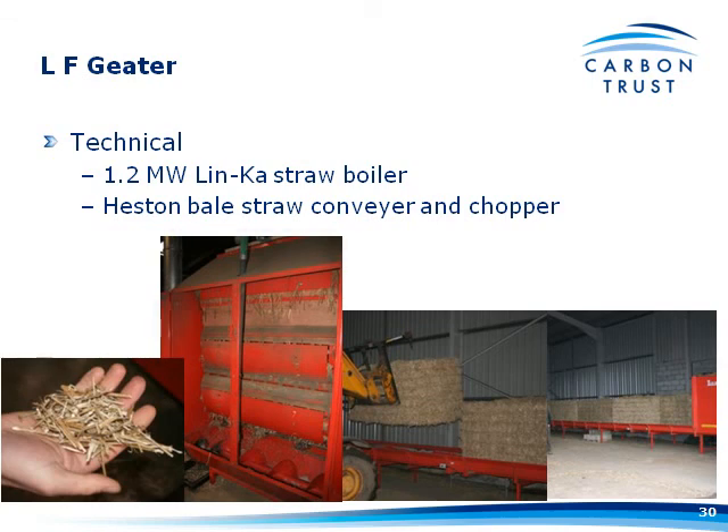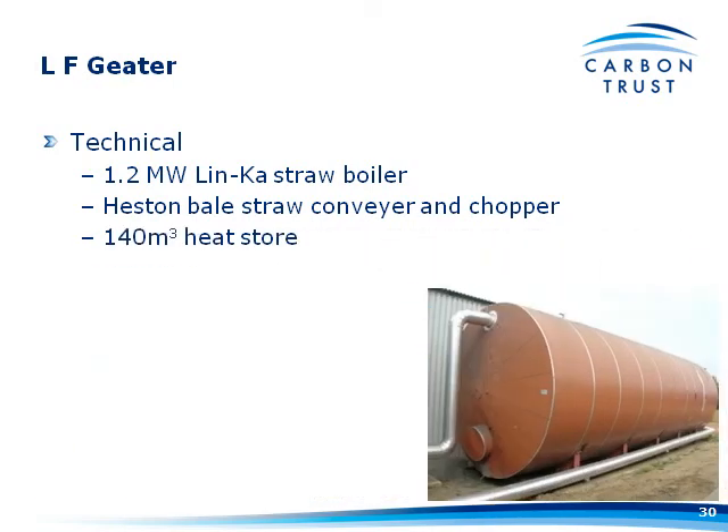The stoker auger in this case is actually a fan at the boiler end. L F Geater installed a 140-cubic-metre heat store — understanding the importance of having one to make the best use of their boiler. They managed to get it second-hand from Holland for about £13,000. It was apparently very interesting getting it onto site around some tight corners. It's very well insulated — a thermal camera shows not very much heat coming off it at all.